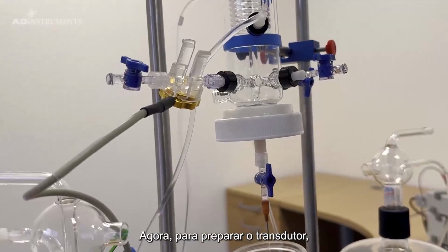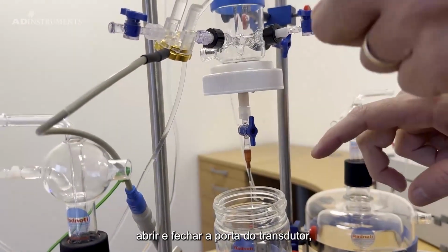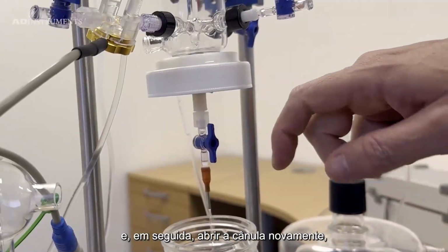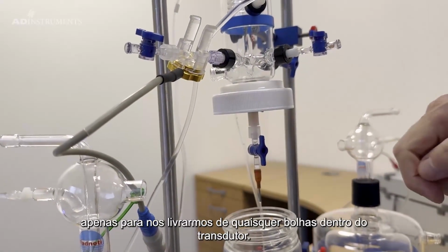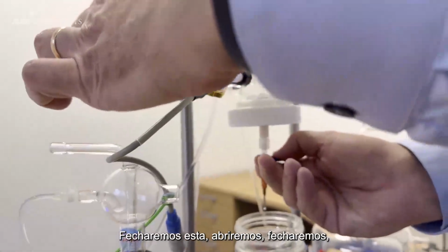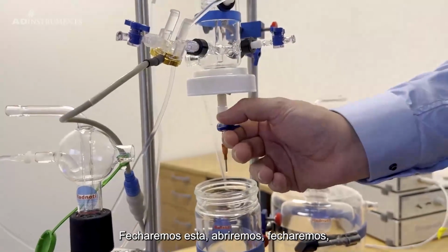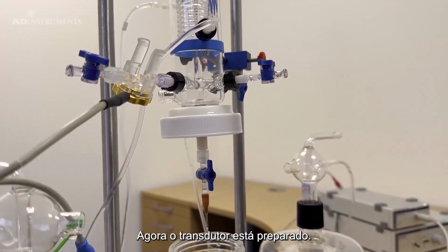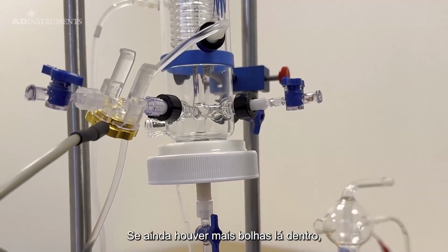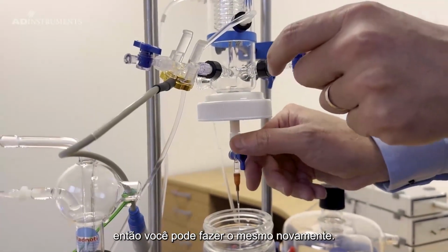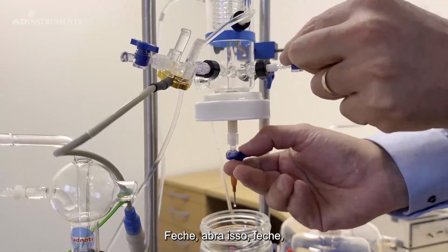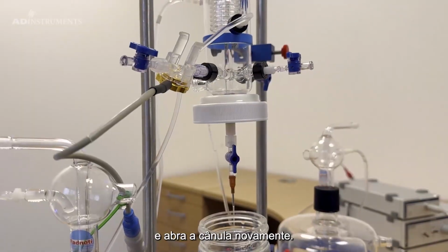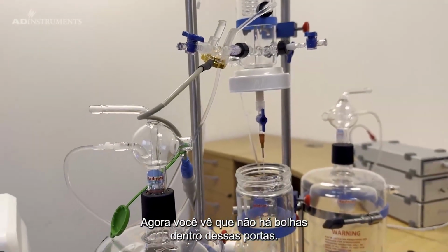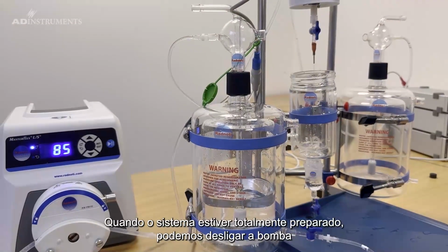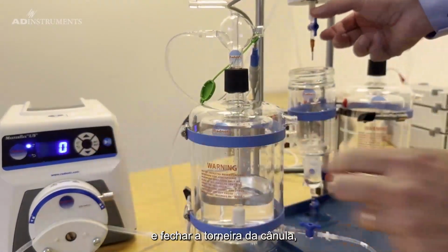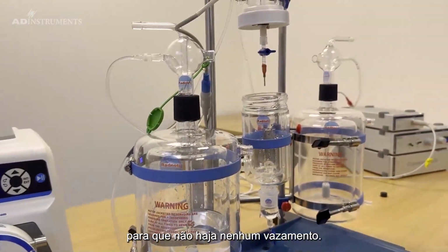Now, to prime the transducer, we're going to close the cannula, open and close the port to the transducer, and then open the cannula again, just to get rid of any bubbles inside the transducer. So I'll do that now. We'll close this, open, close, and then open the... So now the transducer is primed. If there are still any more bubbles in there, then you can do the same again. Close, open this, close, and open the cannula again. Now you see there are no bubbles inside those ports. Once the system is fully primed, we can switch off the pump and close the tap to the cannula so that we don't have any leakages.